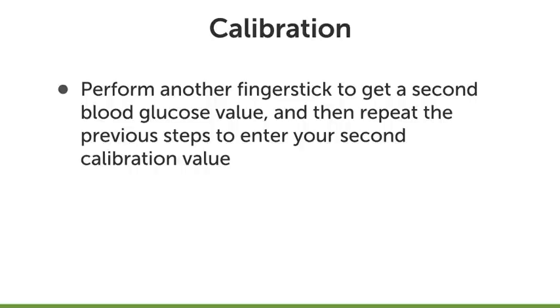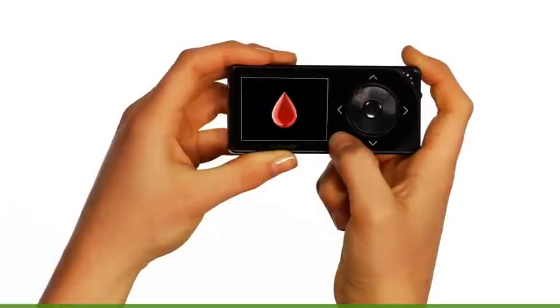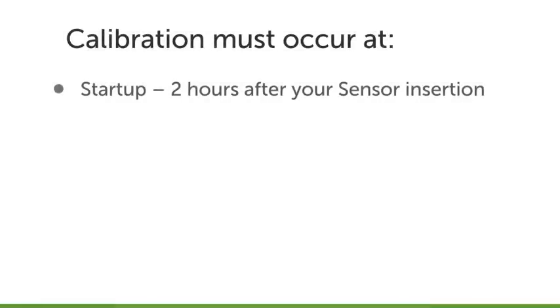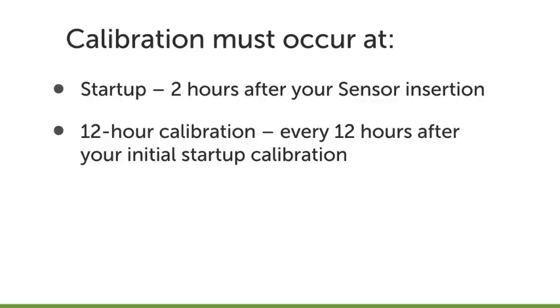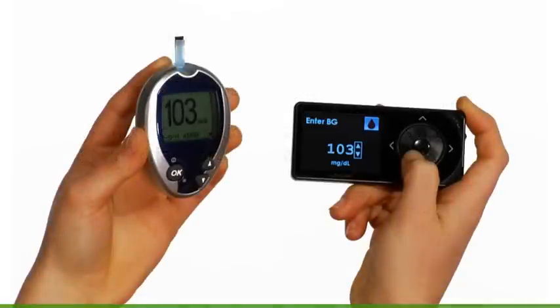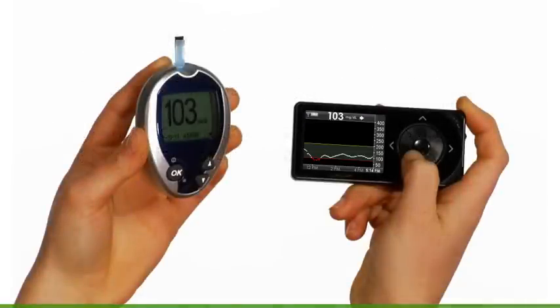Throughout your 7-day sensor session, the calibration prompt will appear to let you know it is time to update your calibration by entering 1 fingerstick blood glucose value. Calibration must occur at startup, 2 hours after your sensor insertion, and then as a 12-hour calibration, every 12 hours after your initial startup calibration. You can calibrate more frequently if desired. In some cases, during your sensor session, you may be prompted to enter additional calibration updates if needed.